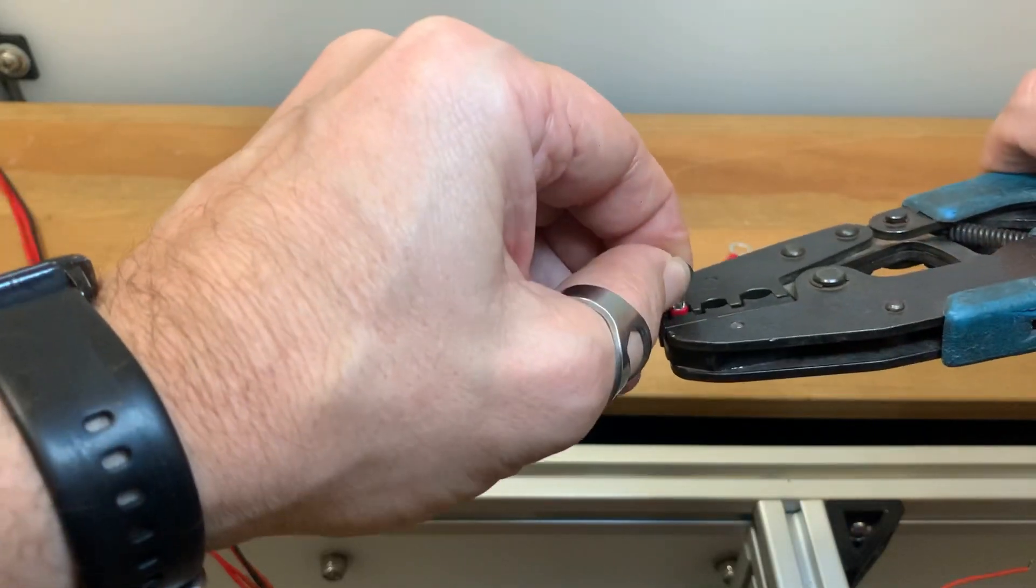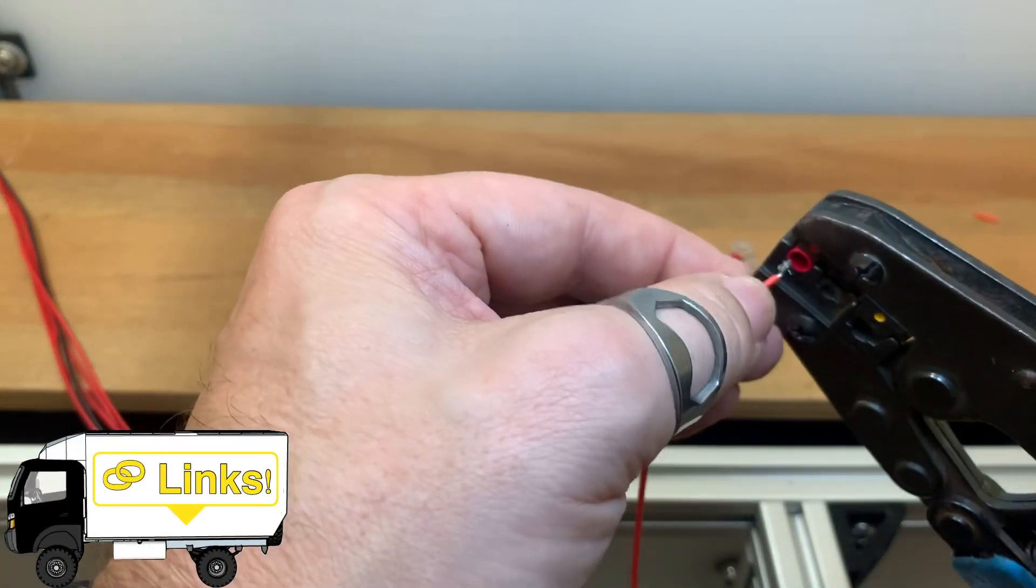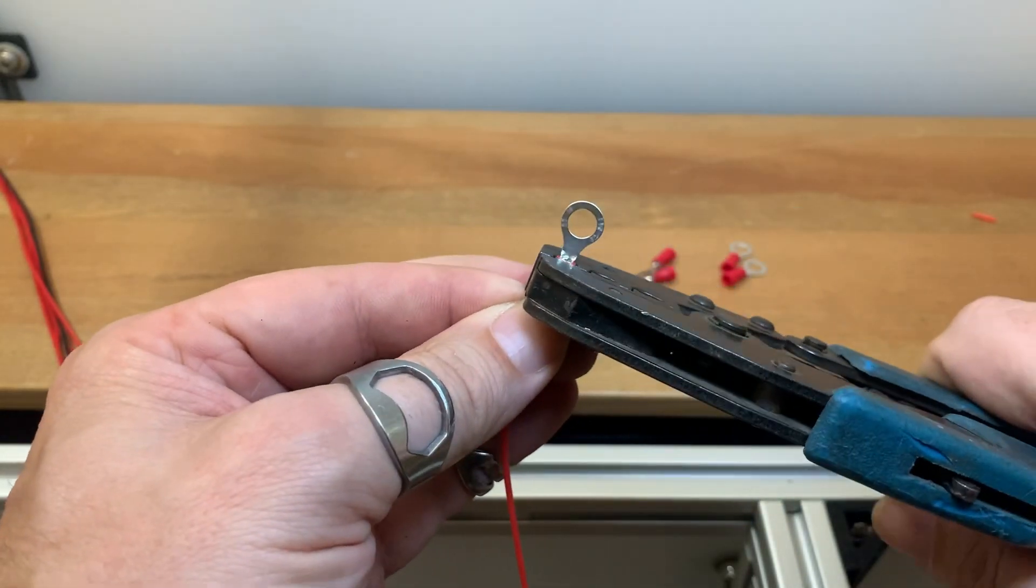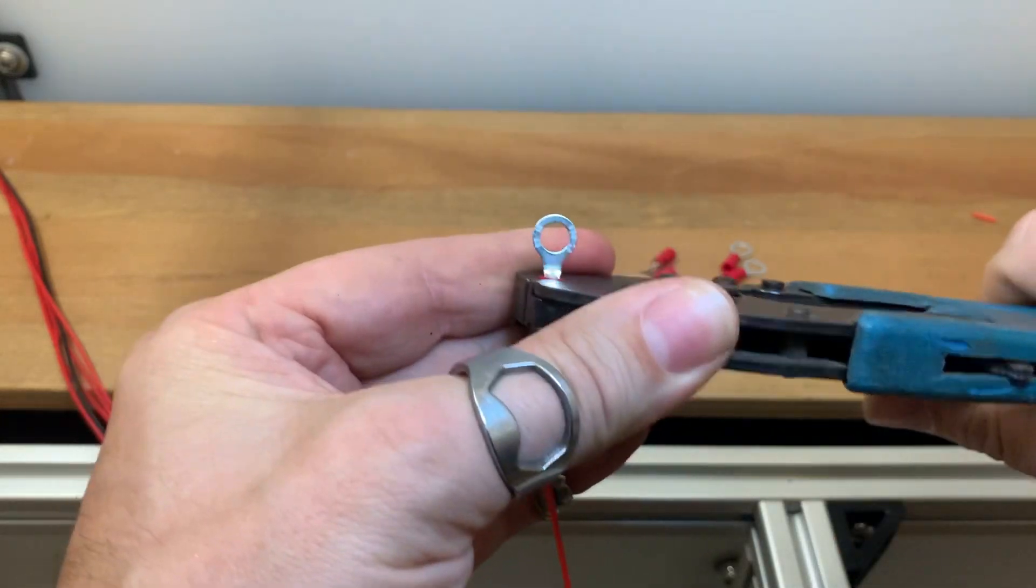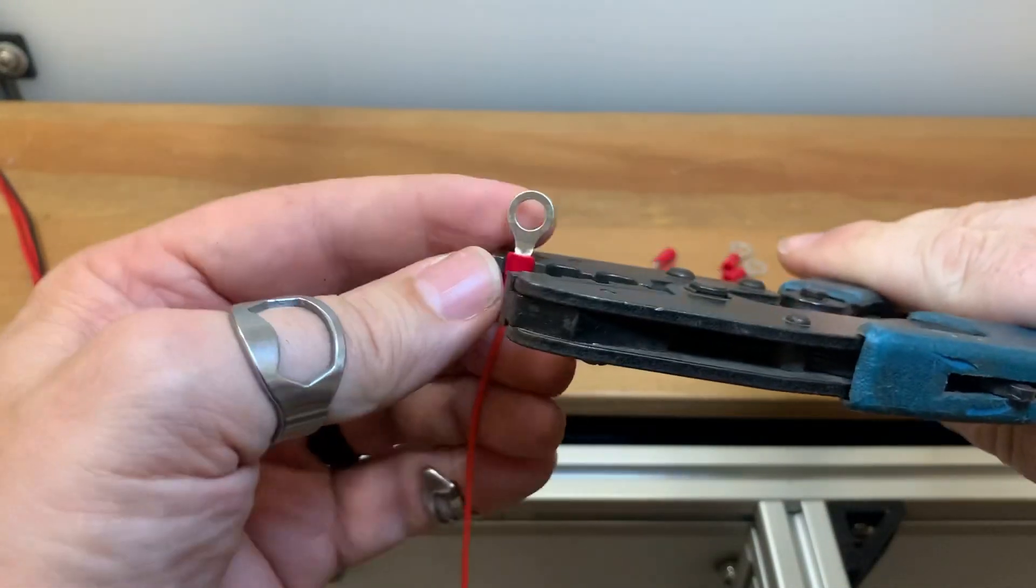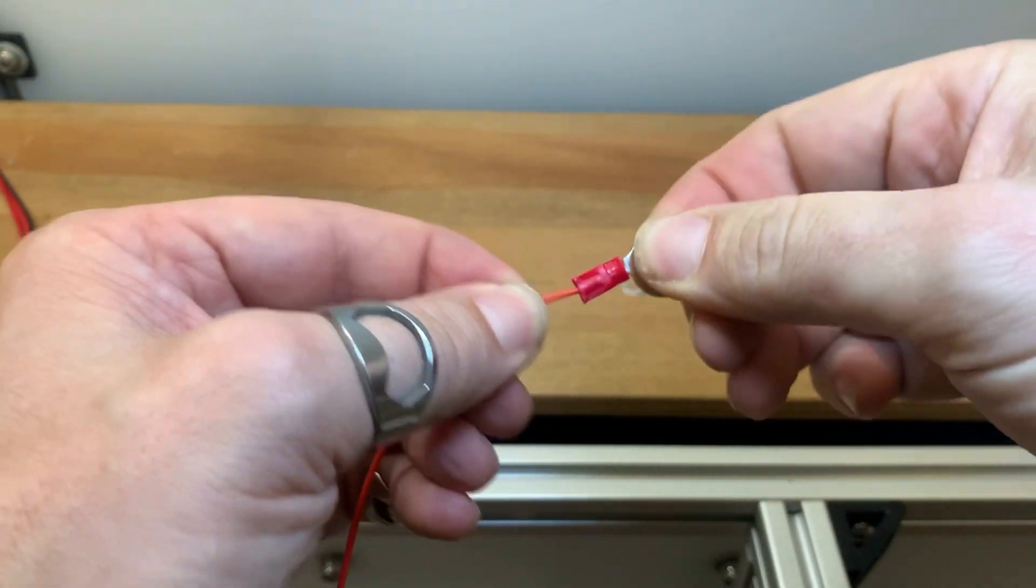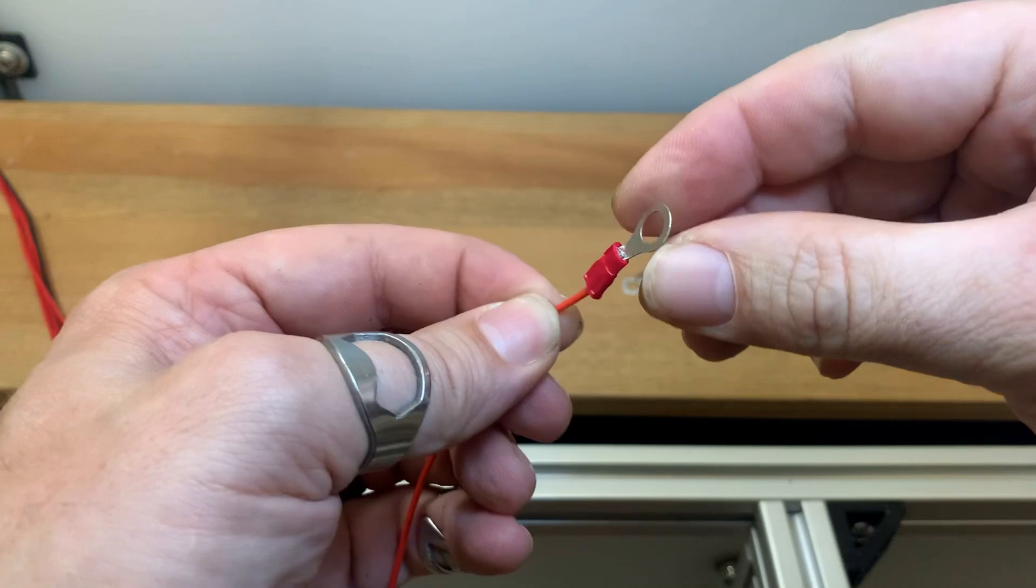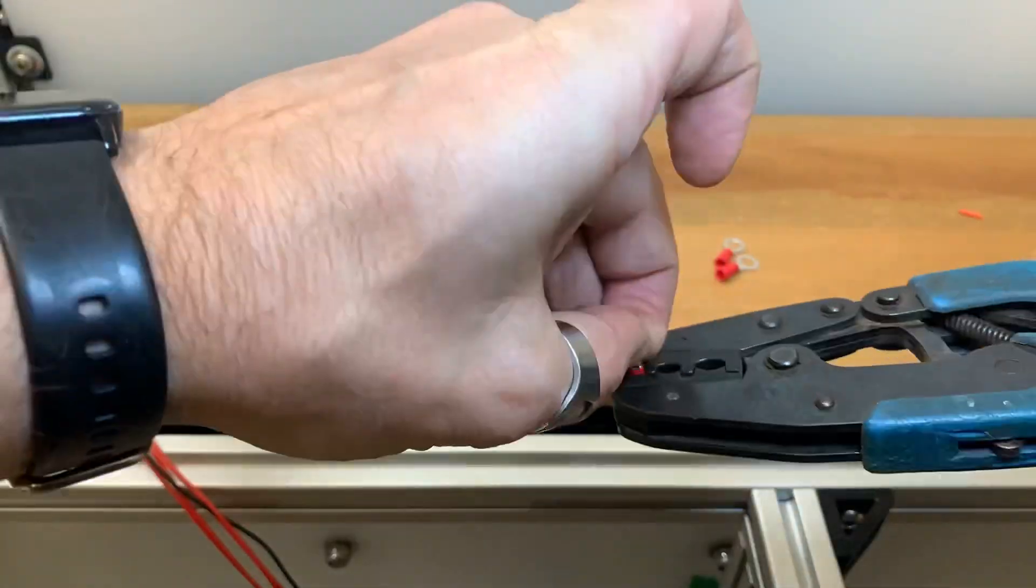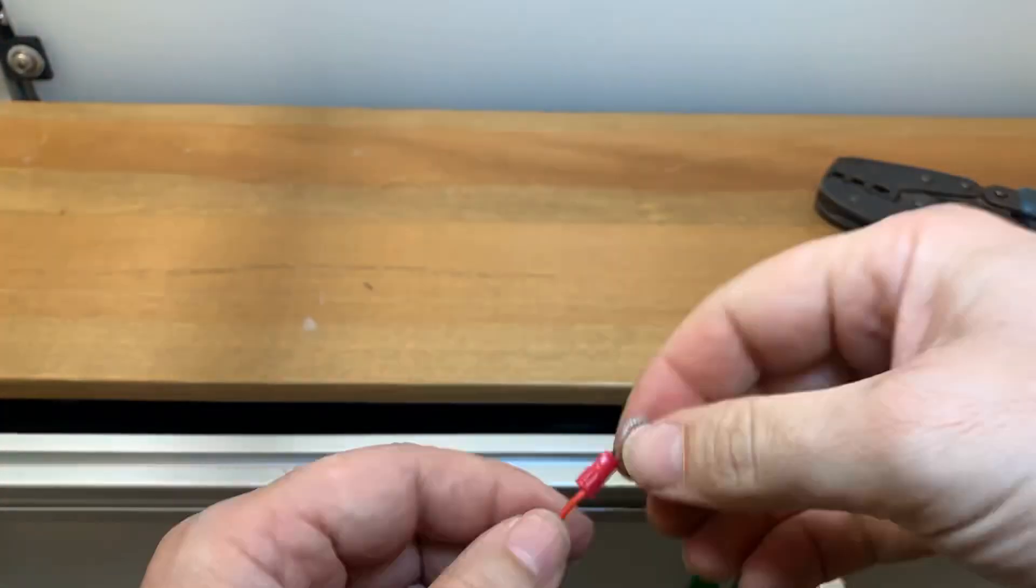I highly recommend only using ratcheting style crimpers versus the cheap stamp type. Ratcheting crimpers only release after a full compression cycle so you don't have under crimped connections which can pull apart or add resistance to your circuit. After your crimp is complete, always pull test your crimps every single time. I've had these crimpers for over 20 years and I bought them used. They've seen a lot of use even in a commercial application and they're still going strong.